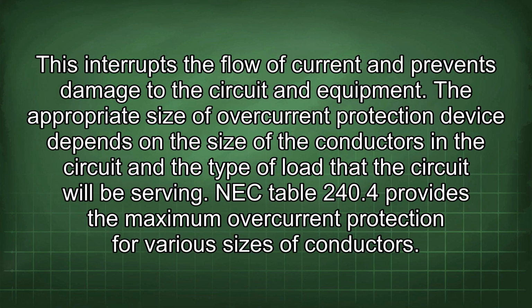This interrupts the flow of current and prevents damage to the circuit and equipment. The appropriate size of overcurrent protection device depends on the size of the conductors in the circuit and the type of load that the circuit will be serving. NEC Table 240.4 provides the maximum overcurrent protection for various sizes of conductors.